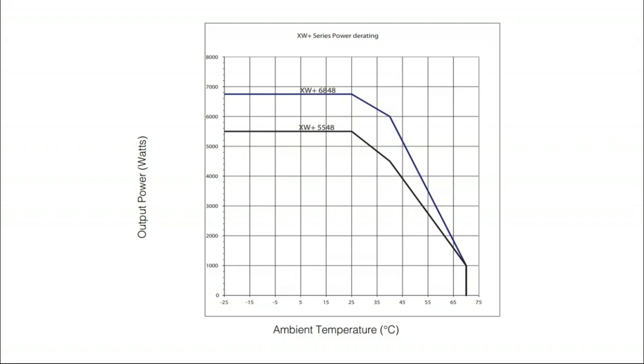Boxes built off to the side are a popular option because it takes the danger out of the house, so they're not a bad deal. But not just the batteries—your battery inverter equipment also degrades at higher heat, so there are overall performance gains from keeping them inside. On top of that, battery inverters have a lot more stuff going on inside them than a regular solar inverter, and so not all battery inverters are as rugged as solar inverters.